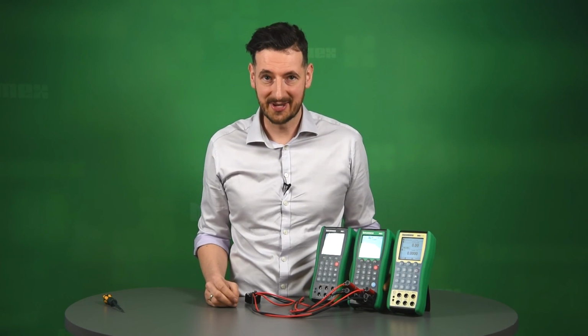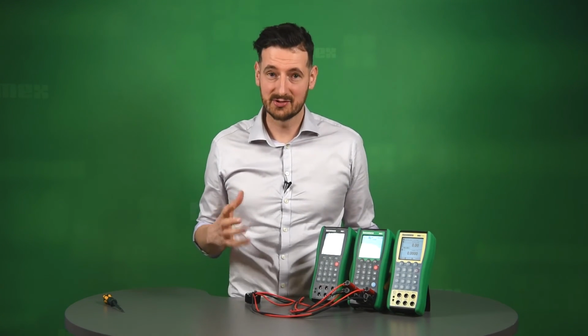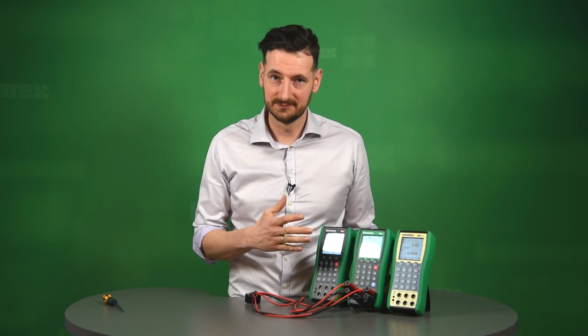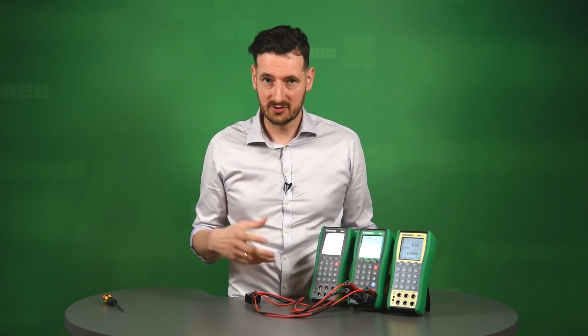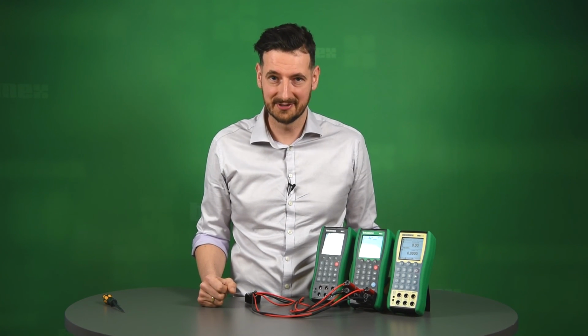There you have it. That's how you calibrate this RTD temperature transmitter using the MC4. You could also calibrate this transmitter using the MC2 and the MC2IS. These are very useful toolbox calibrators, highly recommended.